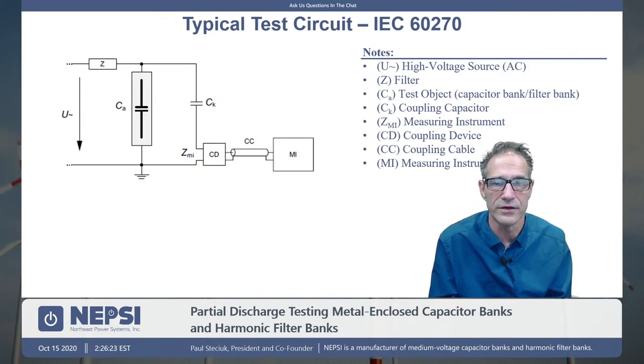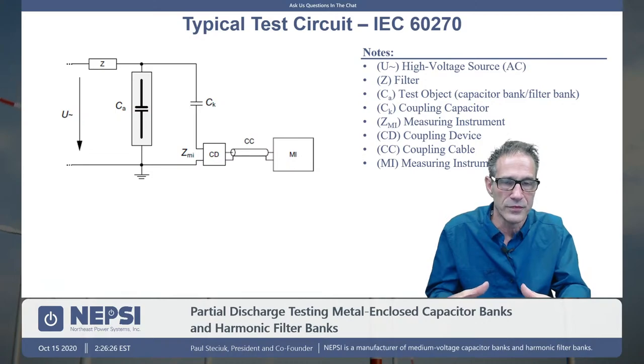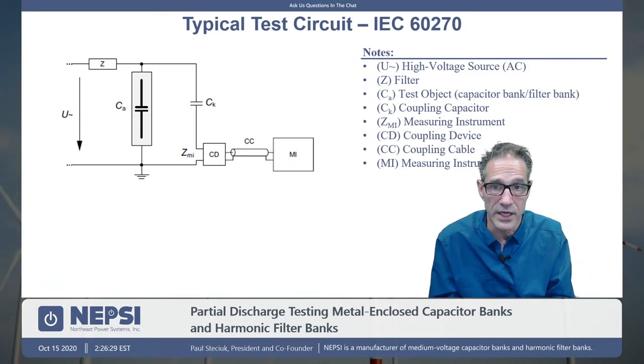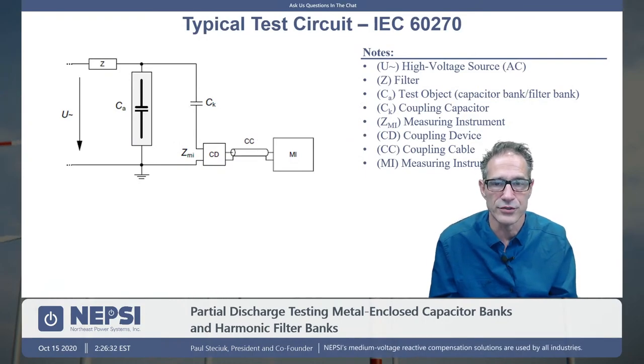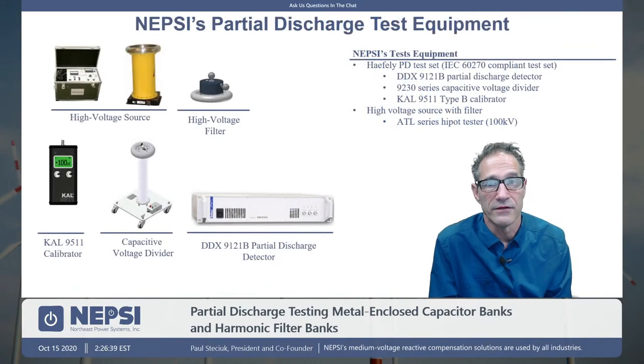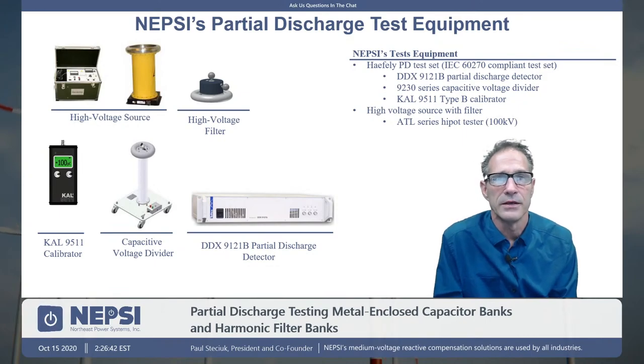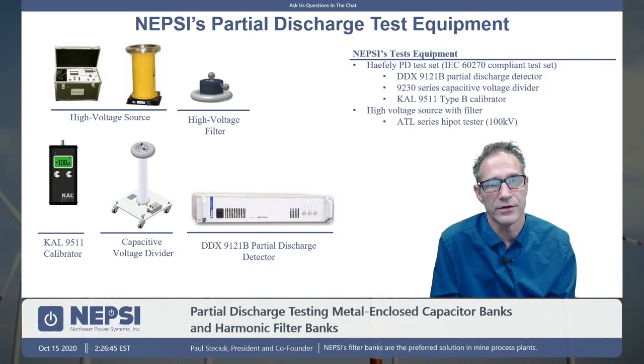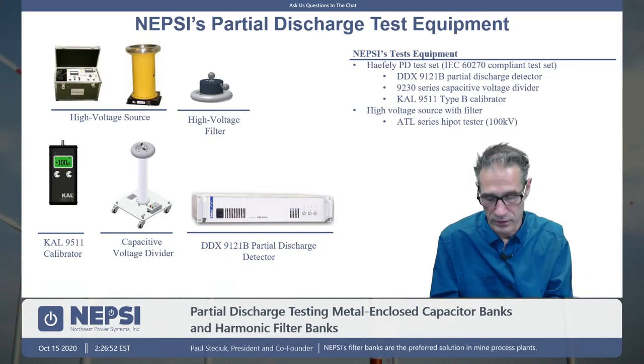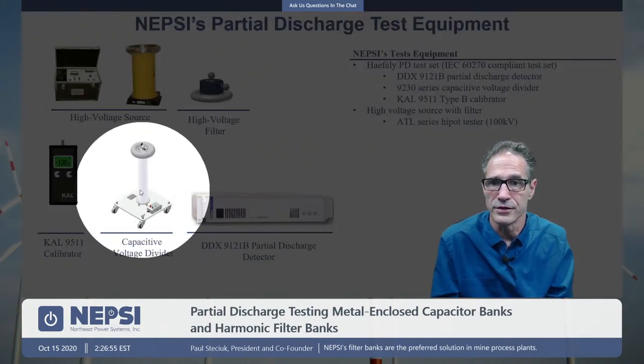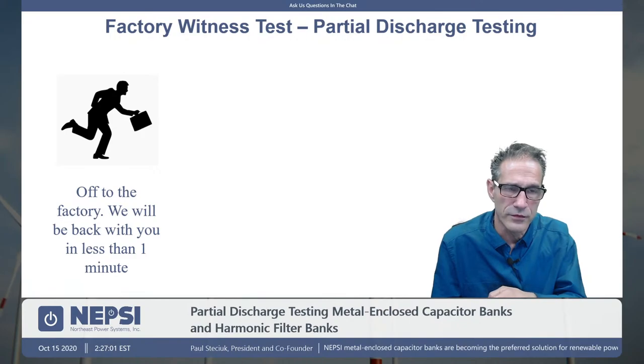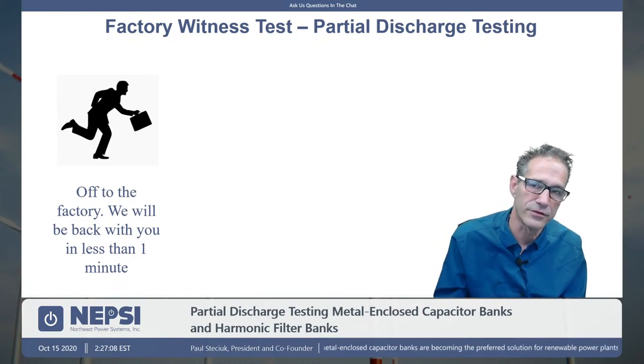And then you have CD, the coupling device, which you're going to see at the bottom of our coupling capacitor. And we run a cable over to this device called MI, which is a measurement instrument. This is a system that we purchased from Haefely. It's based upon 60270, and it's a test procedure and method for evaluating partial discharge. And these are basically all the elements of this test equipment. You're going to see it in just a minute live for yourself. So I think we're about there. I'm going to go back to the factory floor. We have a piece of equipment out there. Pete and Jessica are there with the test equipment.